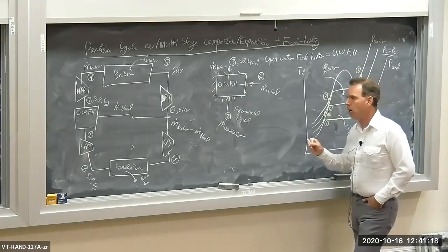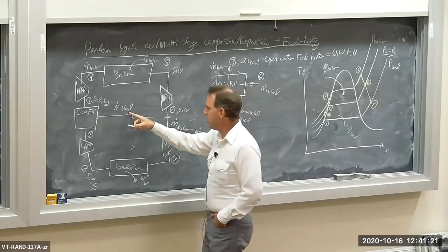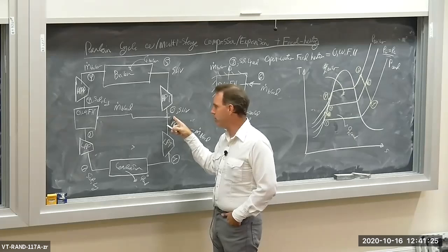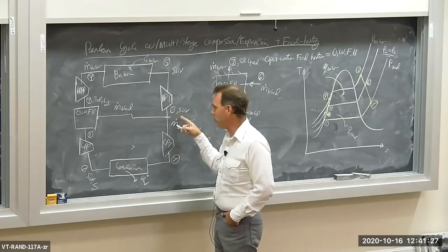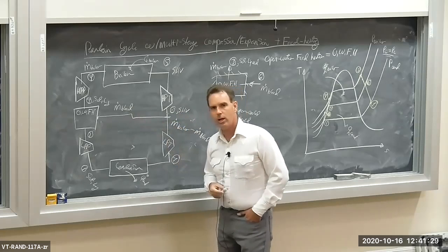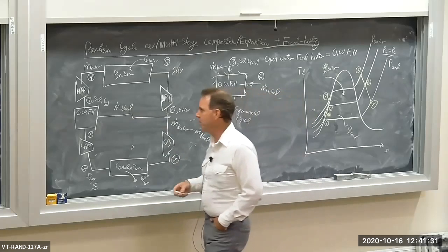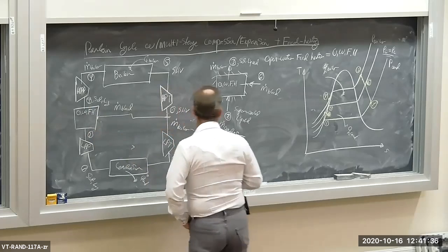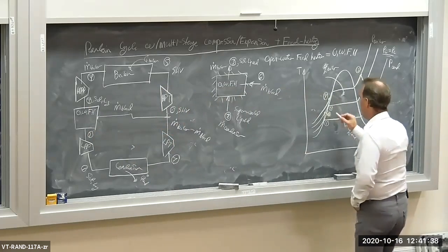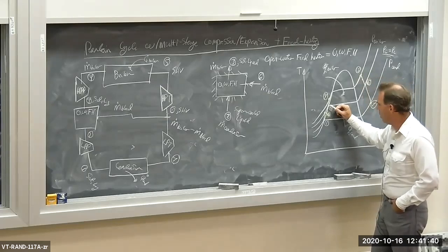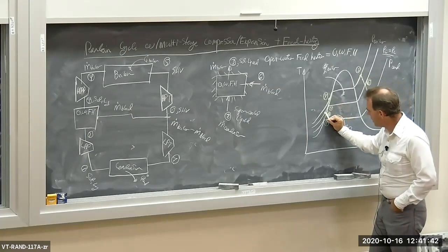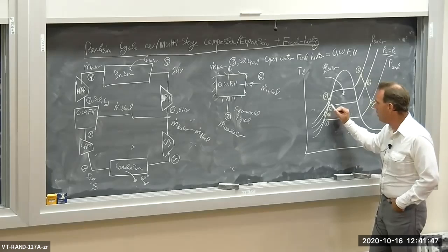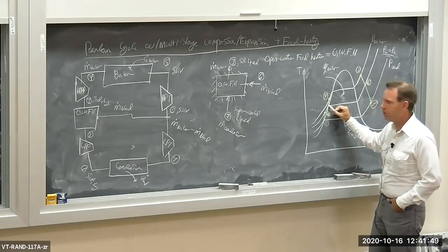Now we're going to bleed off just enough intermediate pressure, superheated vapor steam to heat up the liquid water to a saturated liquid at the intermediate pressure. So on the TS diagram, we're going to take a jump from supercooled liquid at the intermediate pressure to saturated liquid at the intermediate pressure.